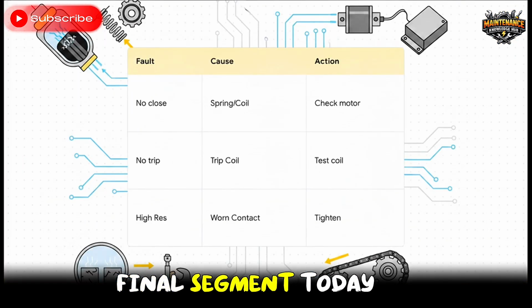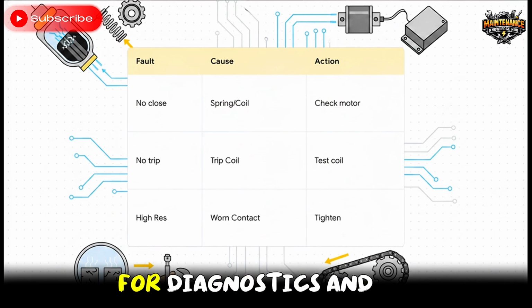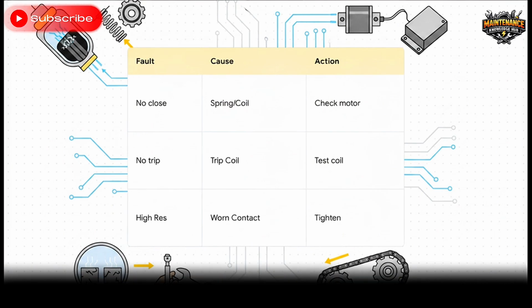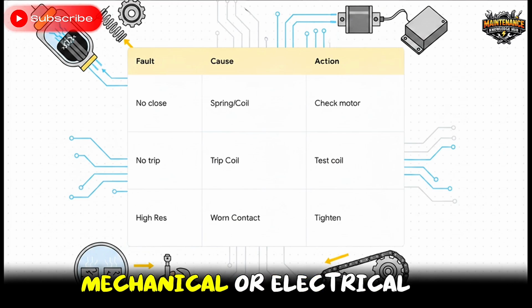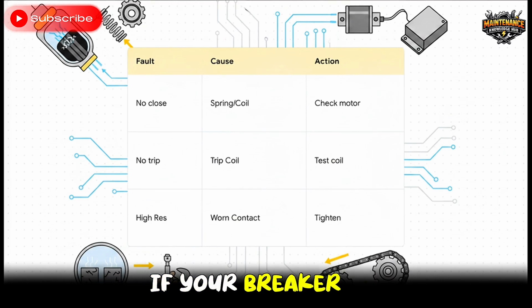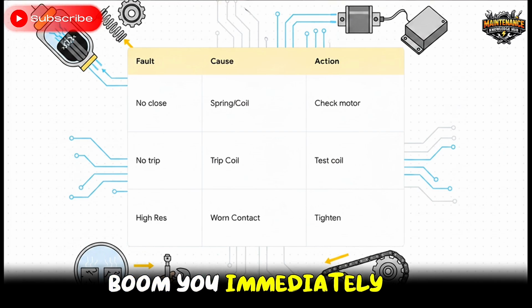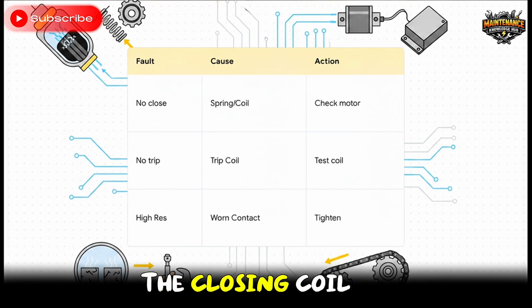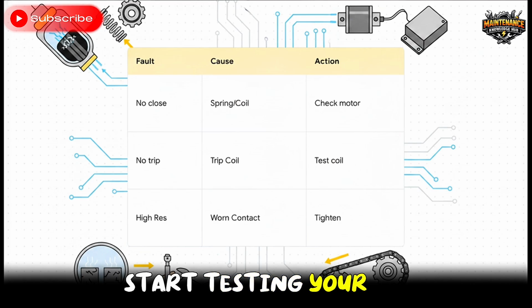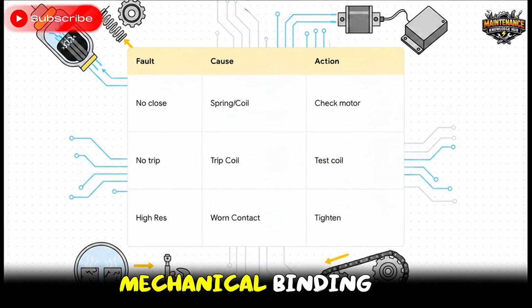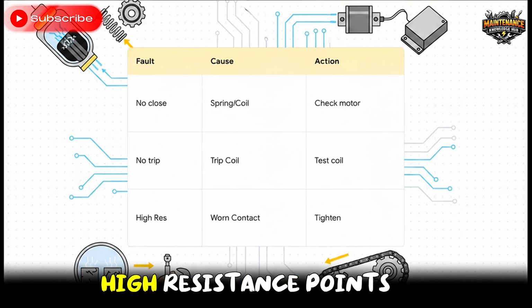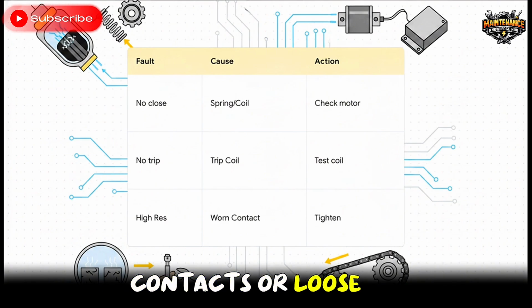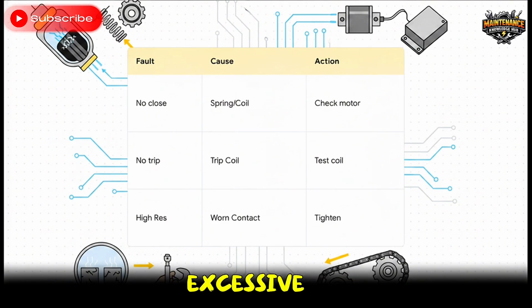Transitioning to our final segment today, let's look at your quick reference guide for diagnostics and maintenance scheduling. Now, what's really interesting about this slide is how neatly the symptoms map to very specific mechanical or electrical fixes. If your breaker fails to close, boom, you immediately look at your charging motor, your spring, or the closing coil. Fails to trip? Start testing your trip coil, the protection relay, or hunt for mechanical binding. Like we mentioned earlier, high resistance points straight to worn contacts or loose terminals. And if the operating time is excessive, well, you almost certainly have a dry linkage or a worn mechanism that's begging to be cleaned and lubricated.